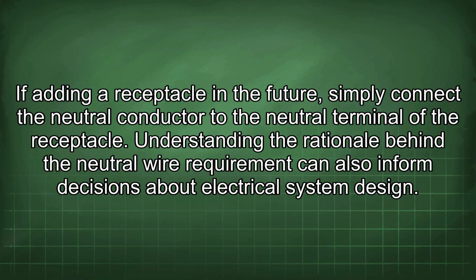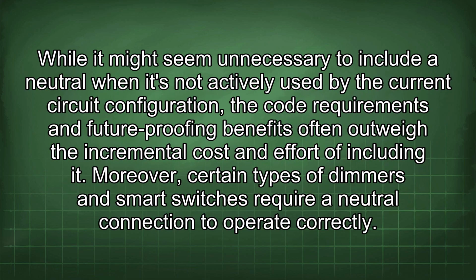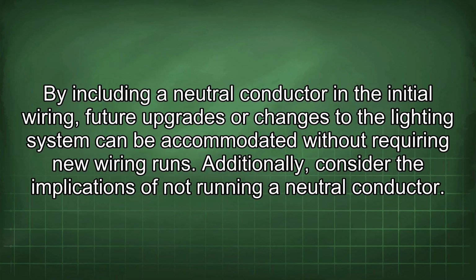Understanding the rationale behind the neutral wire requirement can also inform decisions about electrical system design. While it might seem unnecessary to include a neutral when it's not actively used by the current circuit configuration, the code requirements and future-proofing benefits often outweigh the incremental cost and effort of including it. Moreover, certain types of dimmers and smart switches require a neutral connection to operate correctly. By including a neutral conductor in the initial wiring, future upgrades or changes to the lighting system can be accommodated without requiring new wiring runs.